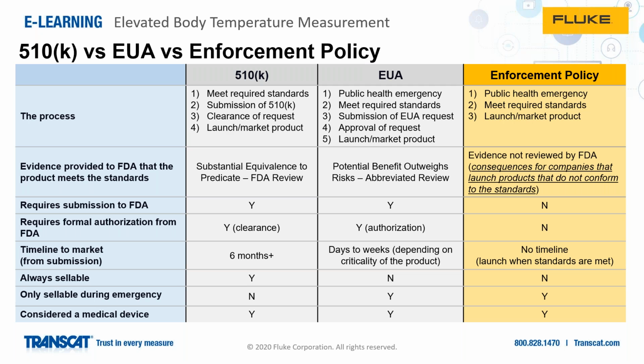when there's no emergency. When there is an emergency, there are 2 other paths to market. There is an EUA, which stands for an emergency use authorization. This essentially requires that there's some sort of public health emergency and that you meet the standards that are outlined in the EUA. You submit this EUA request to the FDA, so you do have to provide some evidence, albeit abbreviated evidence, that you meet. You will be approved of that request, and then you can launch to market under an EUA. And then where most manufacturers are coming to market, particularly with these TI cameras and IR thermometers, is under the FDA's set of enforcement policies.